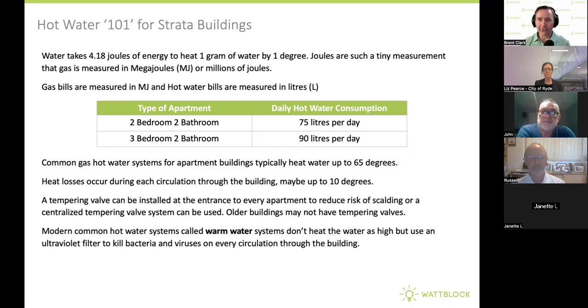Let's get a couple of things in mind regarding hot water. A 2-bedroom, 2-bathroom apartment might use 75 litres of hot water per day; a 3-bedroom, 2-bathroom might use 90 litres per day. If gas is heating the hot water, it's typically heated to 65 degrees. With a common hot water plant circulated around the building, you lose about 10 degrees on every circulation, and the gas hot water plant reheats it for the next trip around.